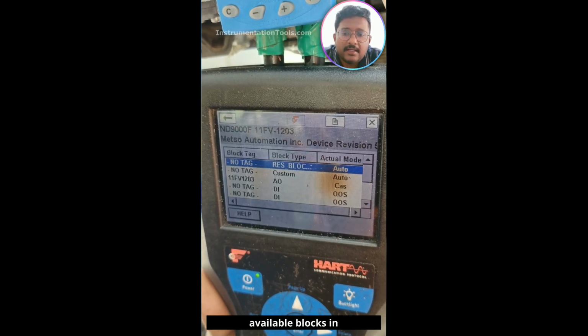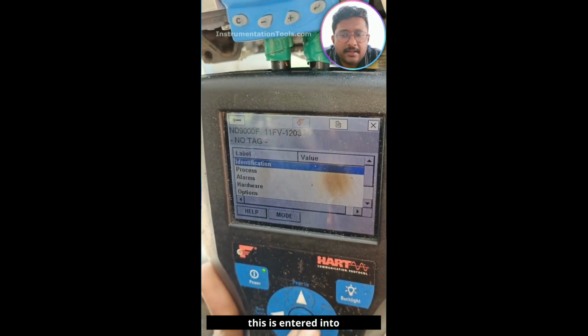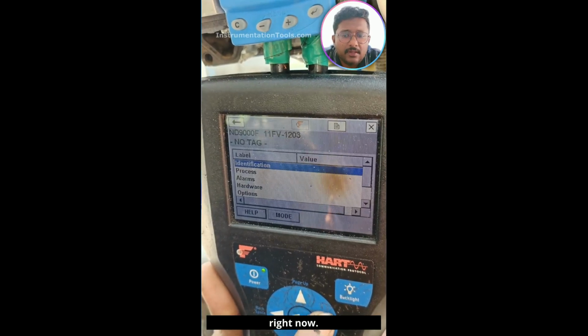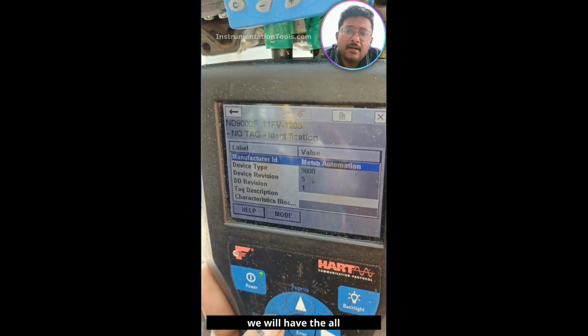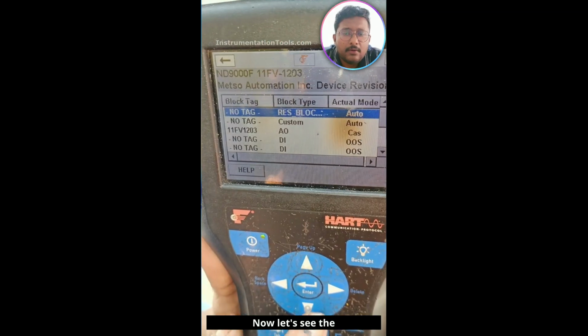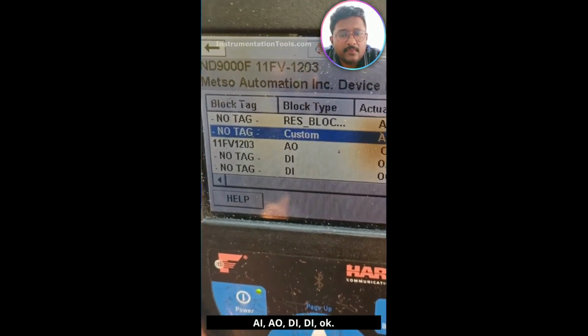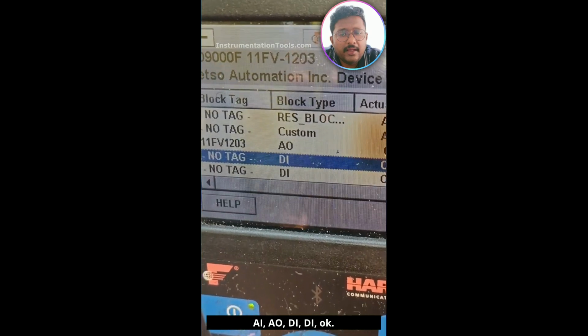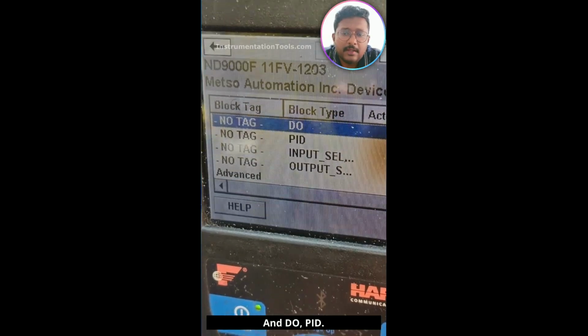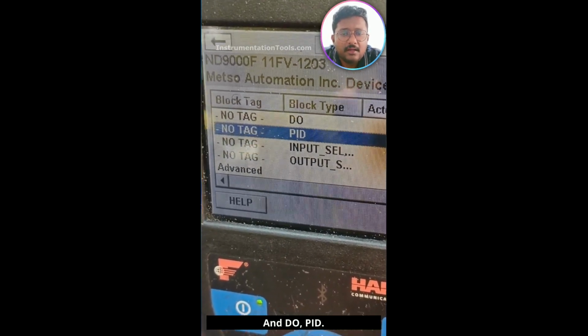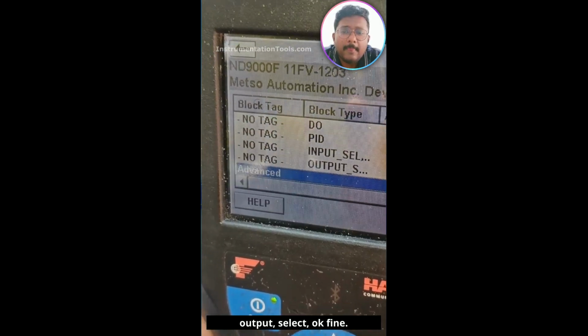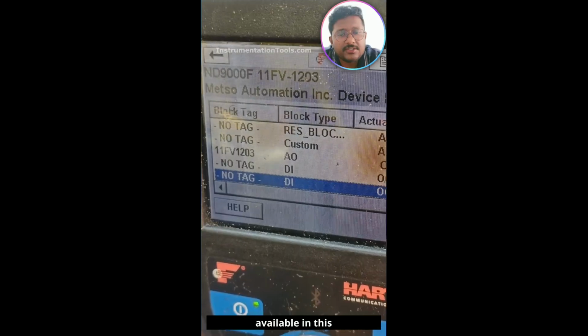Let's see the available blocks in this positioner, and this is entered into the resource block right now. In the resource block, we will have all the parameters related to your valve positioner: the manufacturer ID, device type, model, your device revision, your DD file version. The device description file is very important. Now let's see the block types: AI, AO, DI, DO, PID. This is input select, output select. Okay, fine. So these are the blocks available in this positioner.